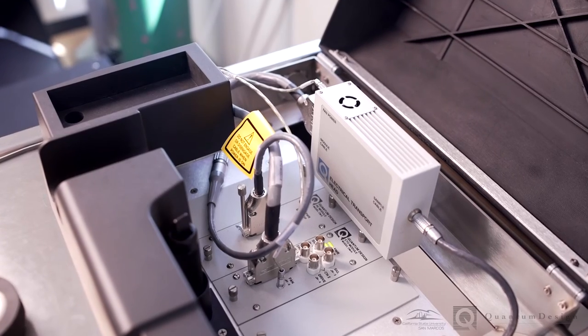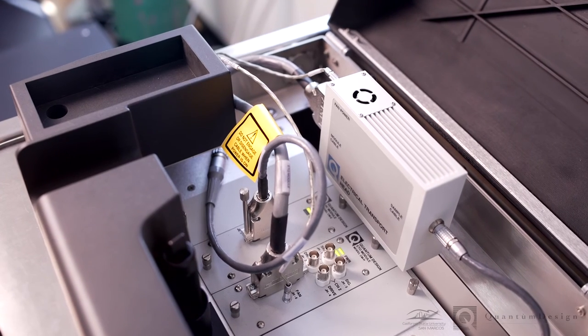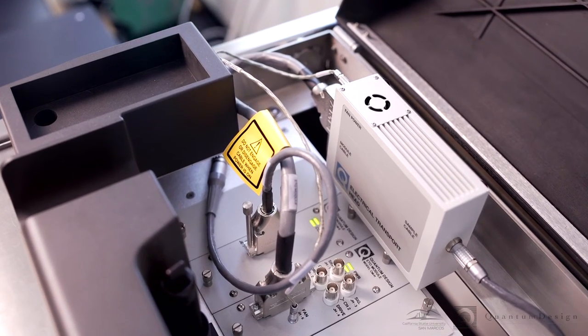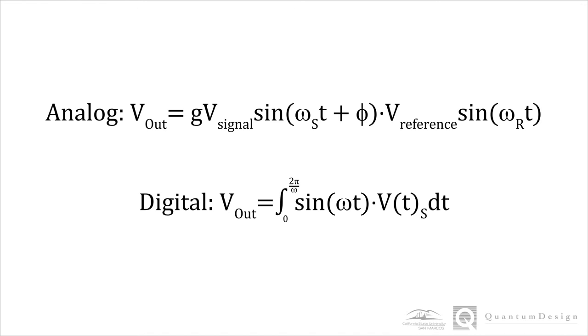Before we perform a measurement with the ETO, we should note that our previous discussion has been about the analog lock-in technique. The VersaLab ETO performs measurements using a digital lock-in technique controlled by the module's digital signal processor, or DSP. Instead of a mixer in a digital lock-in amplifier, the input signal is integrated with a digitally created reference sine wave over one cycle in order to obtain the lock-in result. This has the advantage of being so accurate as to not have the extra harmonics that can be present in an analog reference signal. This output is non-zero if the signal possesses the same frequency as the digital reference.